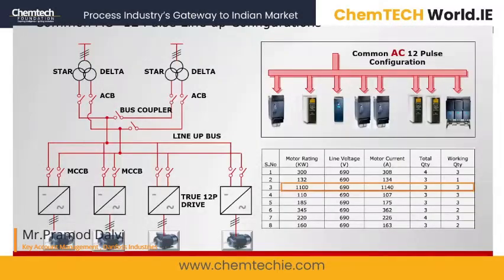So this is the configuration, how it looks when you go for the common AC 12 pulse configuration. You will have 2 transformers and 1 bus coupler. In case one transformer fails, the bus coupler can take it and share it to the other, so transformer redundancy is also ensured. And then if you see, there are 2 inputs going to the drive, one star and one delta. And the red one, the 1100 kilowatt rating, is a very important critical application, which is built on the drive sync feature.